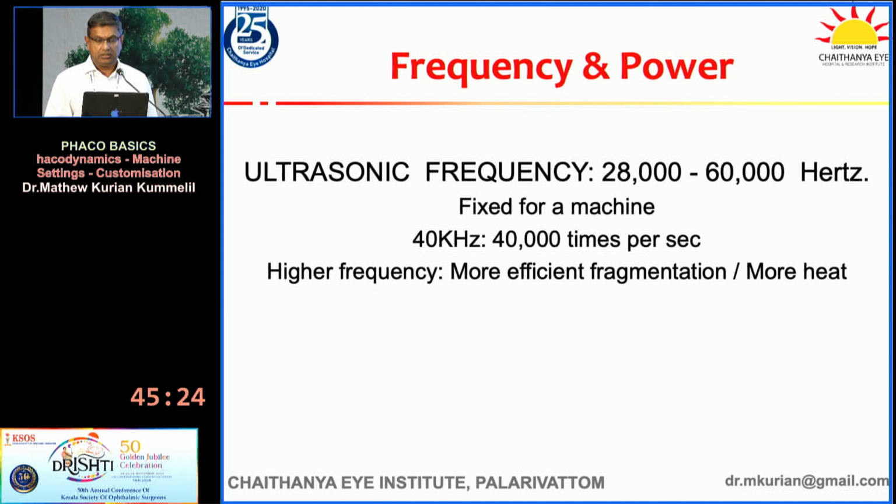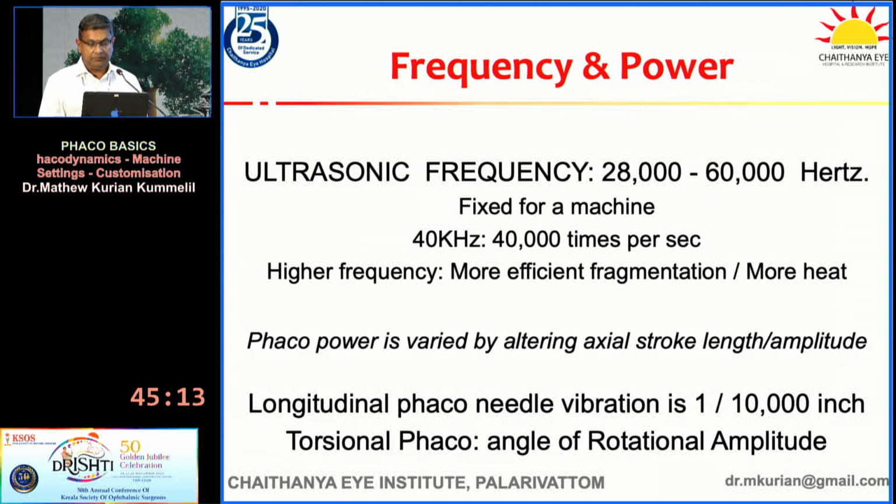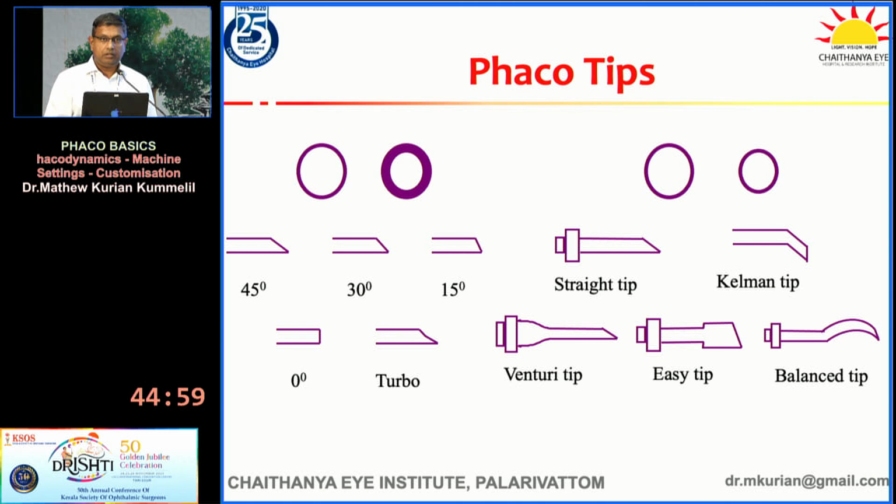The frequency, the terminology is basically the speed at which the phacotip moves, and it is fixed for the machine. The higher the frequency, the greater the efficiency of fragmentation, but also more the heat. The power is varied by altering the stroke length or the amplitude depending on the machine that we use.